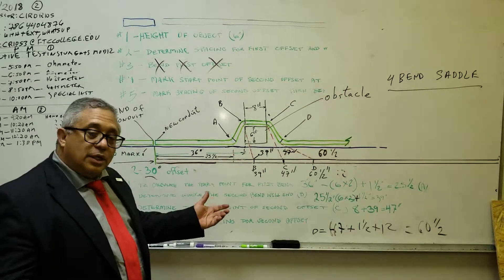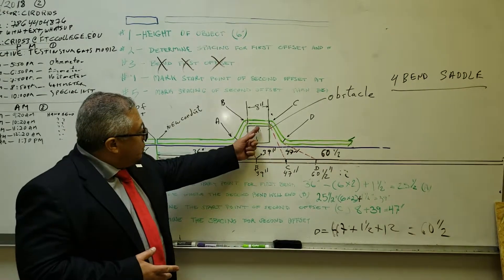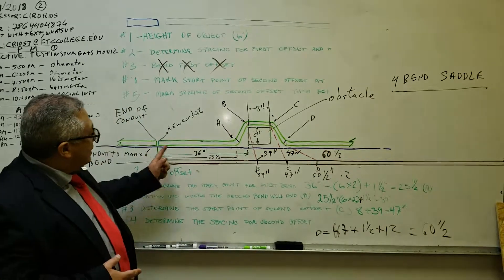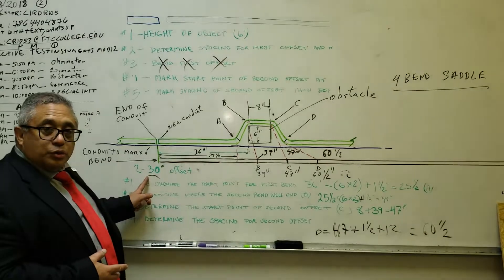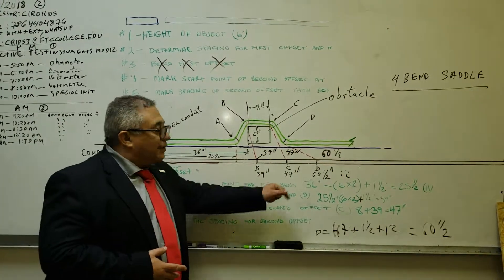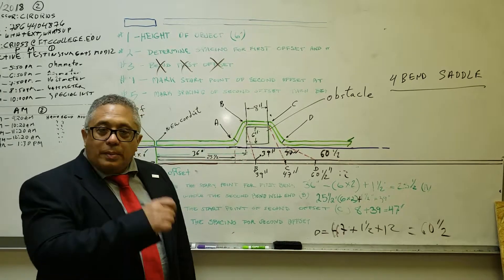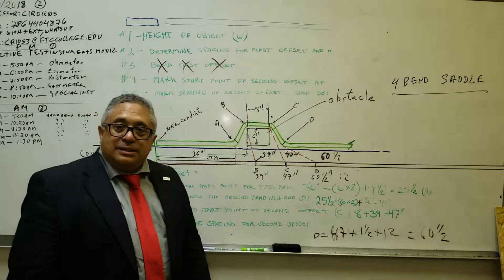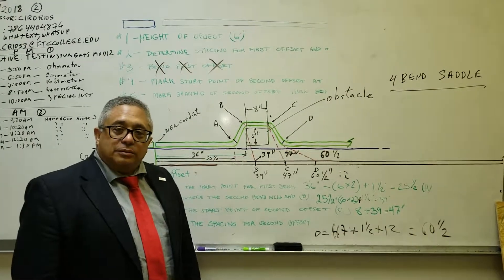In reality, you can download an application to your phone, input the height, the width, the distance to the obstacle, and the angle, and it will give us the 4 points we need to mark the conduit with. We mark it and we bend it. And this is as easy as this. This is how you do the four-bend saddle. Thank you.